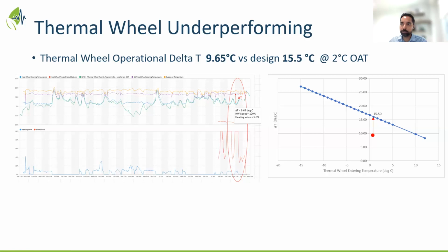So in this hospital, what we recommended is, because we didn't have the air testing reports to confirm whether there's an issue with imbalance in the airflow, or an issue with the wheel not working, or whether the wheel needs cleaning because its performance had deteriorated over a year, or an issue with the media. All of those issues could let your wheel underperform. So the next step in that case is to start with air testing and then confirm that the regular maintenance of the wheel is done and the media is good, so that you get the design values.